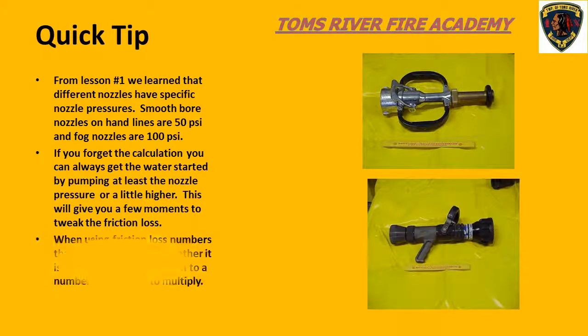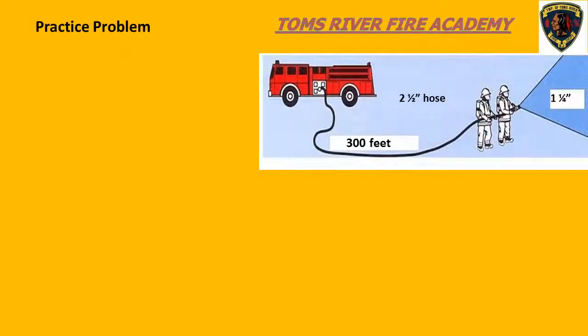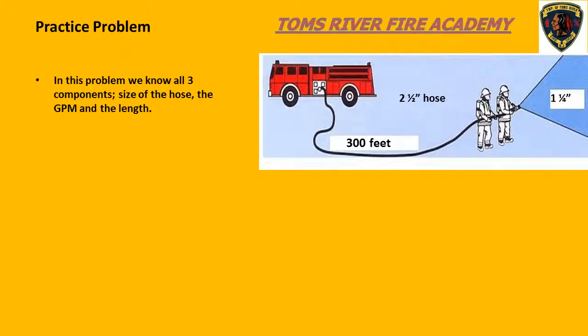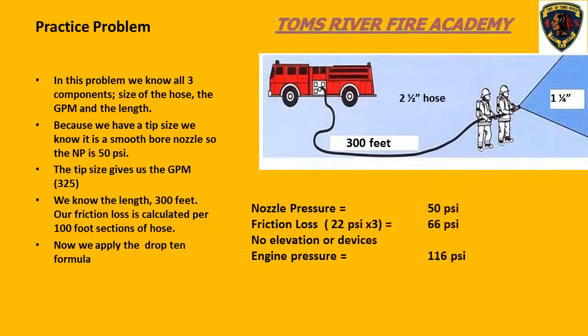Try this practice problem. We know the flow and the size of the hose. The flow is 325 gallons per minute. Using the drop 10 method, we get a friction loss of 22 PSI. There are three 100-foot sections of hose, so the friction loss is 22 PSI for each section. The total friction loss is 66 PSI. The nozzle pressure is 50 PSI. Add these numbers together and you get an engine discharge pressure of 116 PSI.